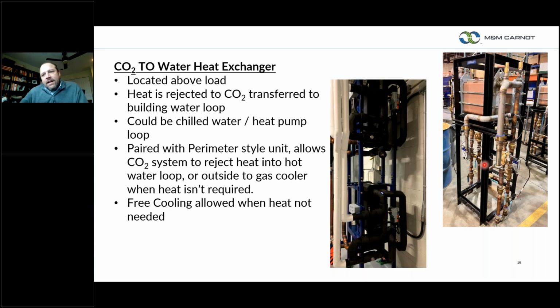So that's one of the exciting things that we're looking forward to in the future, a perimeter style unit with heat that could be rejected into the loop. The heat exchanger I'm showing on the right side is another CO2 to water heat exchanger. This is one that we typically hook up to our row-based units when you're hooking it up to a water loop. It's uninsulated, but I just wanted to show you our stainless steel piping connections coming out on the left-hand side, kind of right at you, but you also have your hot or chilled water piping connections in the middle. So this is 2 heat exchangers, and one of these heat exchangers could serve 2 row-based cooling units.